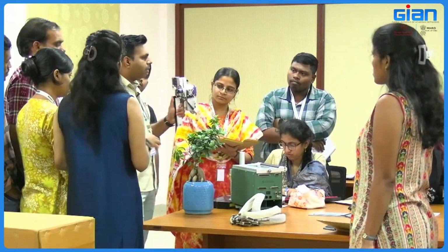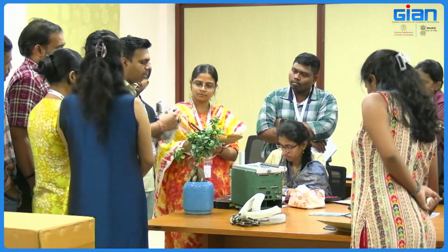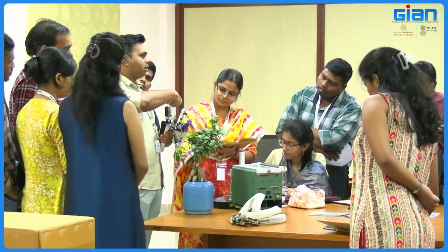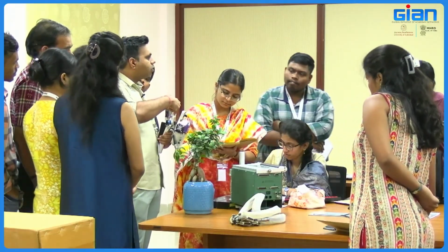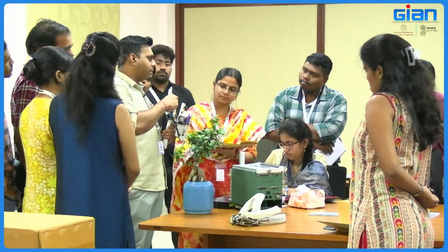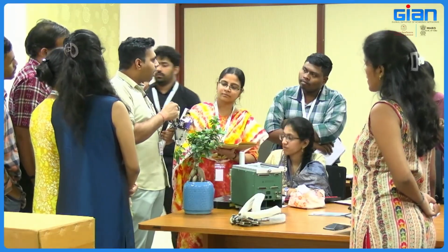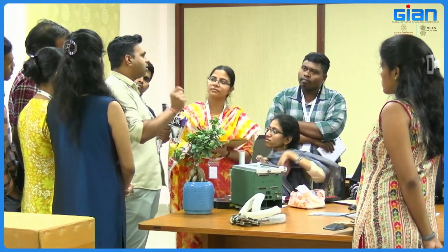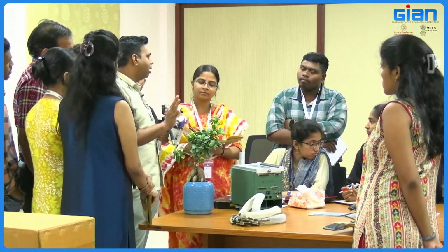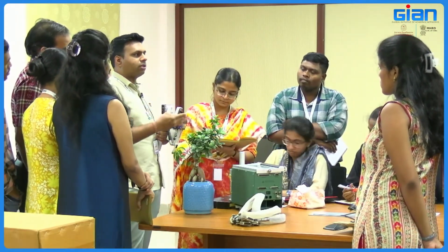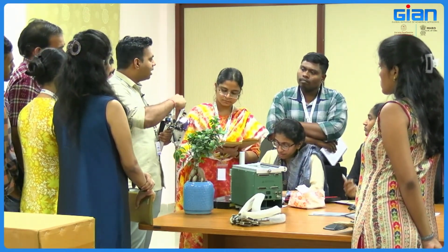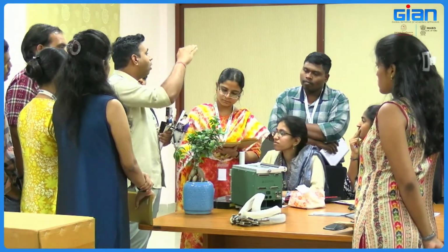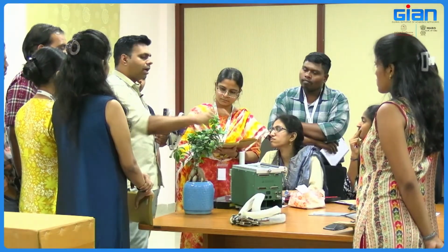So what does the chamber consist of? The chamber here, if you see the top, an LED source is there. Okay, apart from the LED source, infrared radiations are also applied. Got it? Why are the infrared radiations applied? I already told you, it has to detect the heteroatomic molecules, that is the CO2. Okay, only CO2 it will detect. So whatever CO2 levels are inside this chamber, it will compare with the reference CO2, and if it is dropping, it will calculate how much drop is there and show it here.